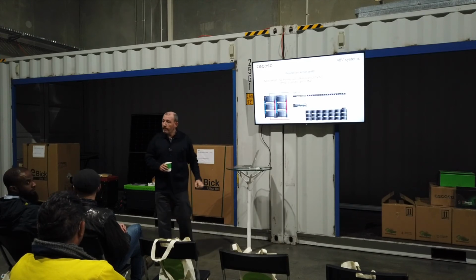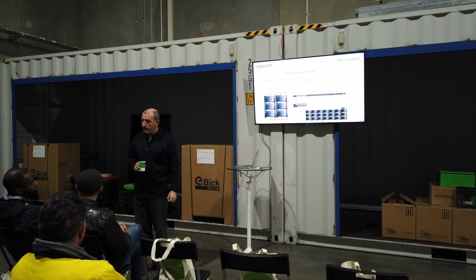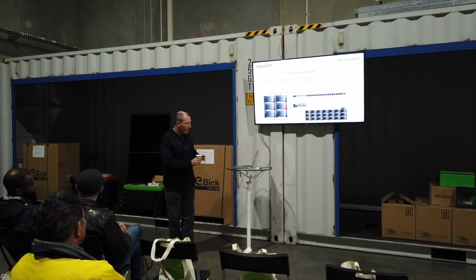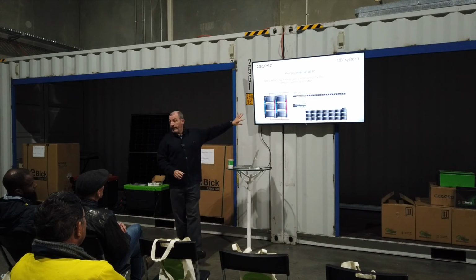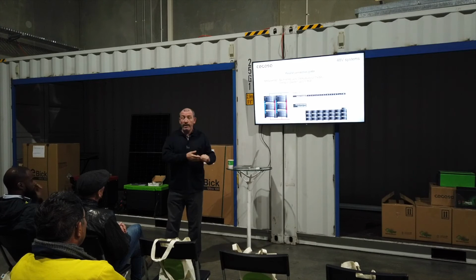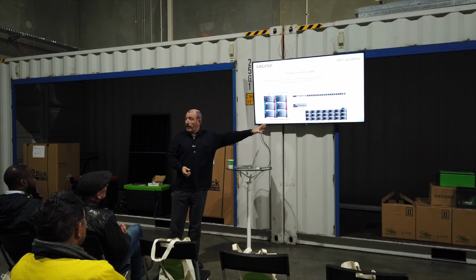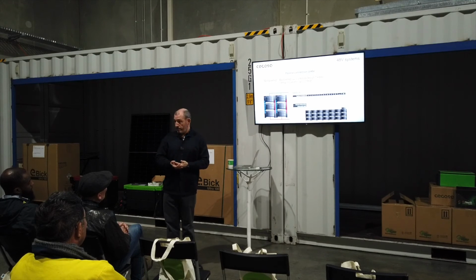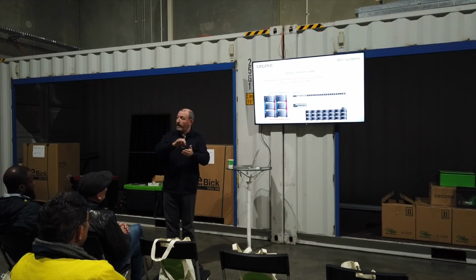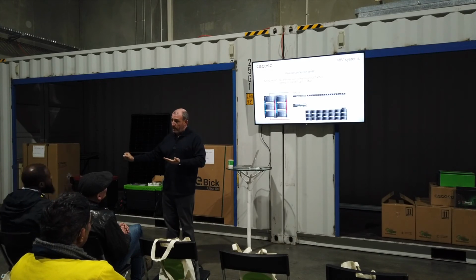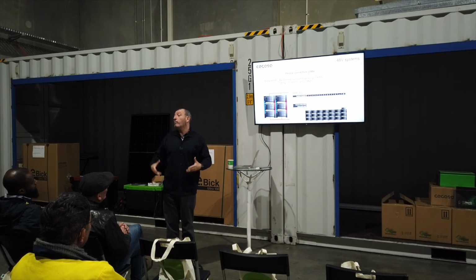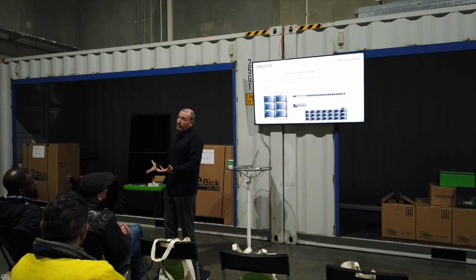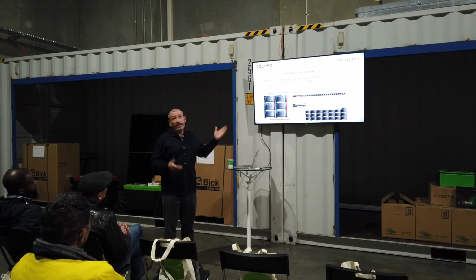So the output of the battery, we just plug into the MCP, then the inverter? Yeah, there is - I'll show it slightly later. Because we're talking parallel connections, there's a recommendation to use a bus bar. They go to the bus bar, and from the bus bar they go to the MCP. We even have a proprietary bus bar, which is not mandatory, but it's something we offer because it's an inexpensive option that matches with the rest of the system and is quite easy to connect, and that's the one that goes into the MCP.